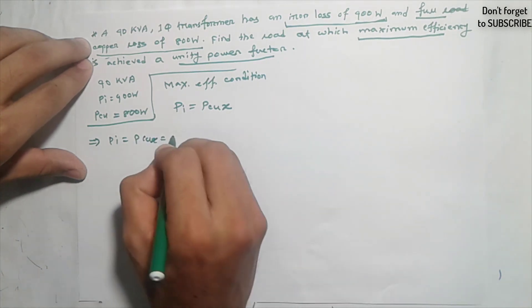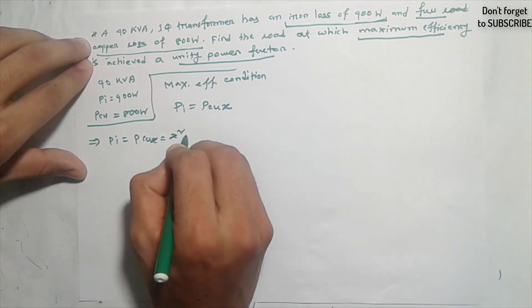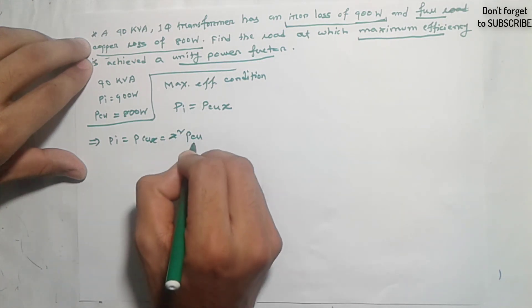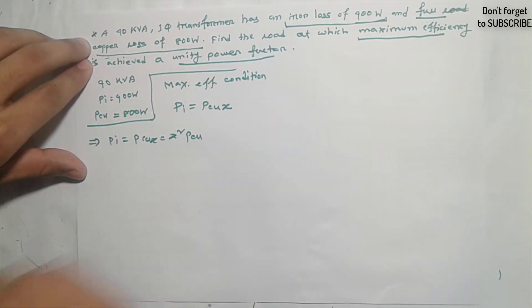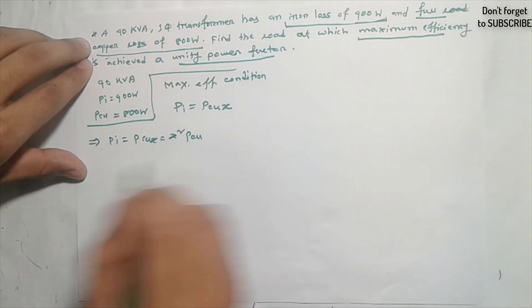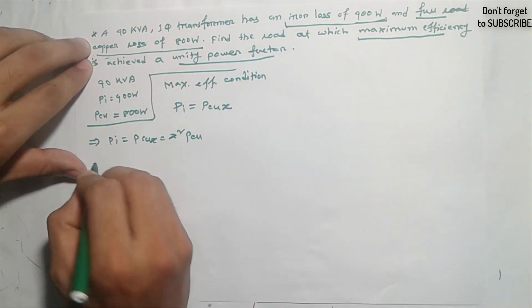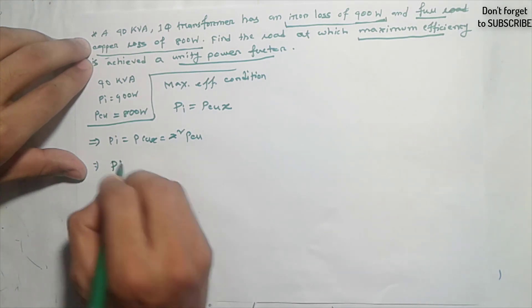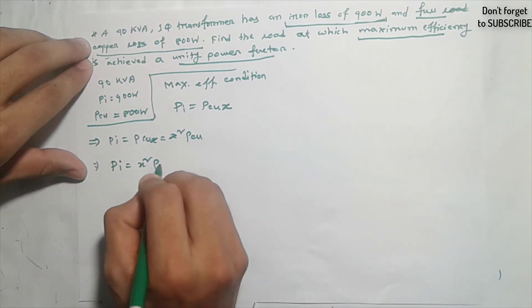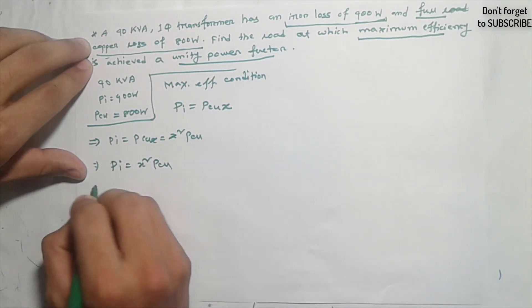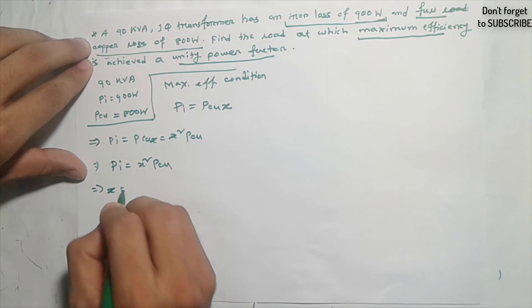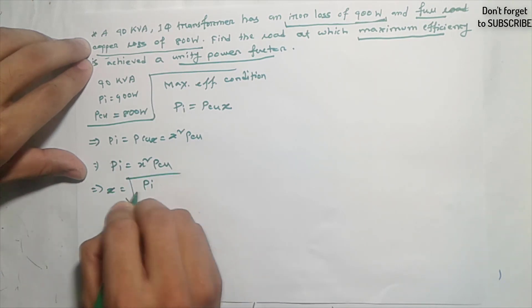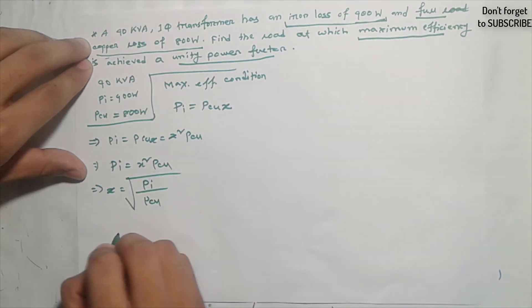PCU(x) equals x squared times the full load copper loss. So PI equals x squared times PCU full load. Therefore, x equals the square root of iron loss divided by full load copper loss.